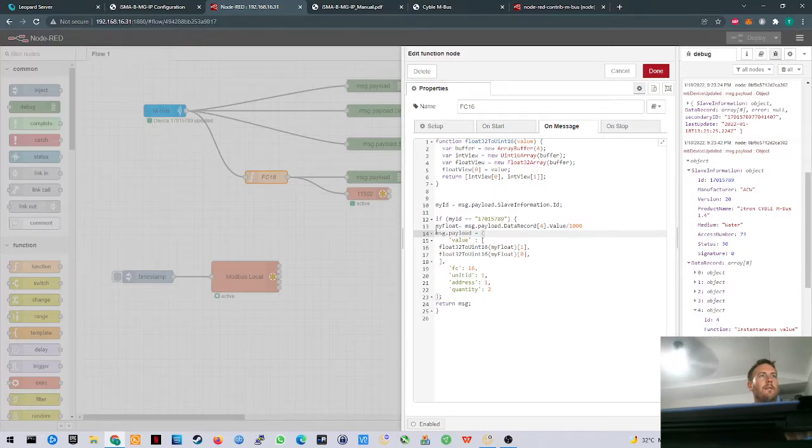And I found this function online. It just works to do what I said before, which is convert that value, it's going to be like 3.563, into two integer values. And then I write that to a Modbus device. So write multiple registers, function code 16, the unit ID of the Modbus, the Modbus ID basically is 1. The register address is 1, and the quantity is 2. But if it's, say, a different device, say it picked up 2 on there, then it wouldn't do anything. So this part only occurs if I'm looking at the correct device.